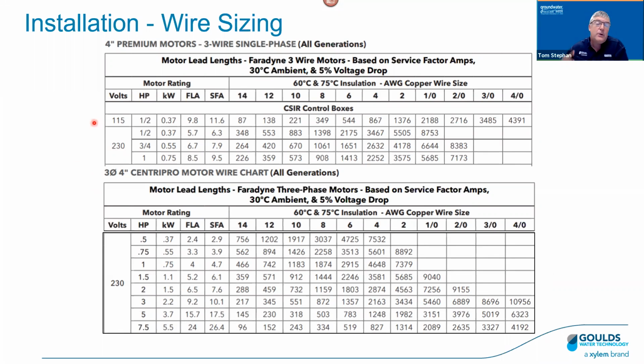So, one thing is we need to know the voltage, and we need to know the horsepower. If we have the model number, we have all that information. Manufacturers are all a little bit different, so it's a good idea to use the particular manufacturer's wire sizing charts, because the amperage does tend to vary a little bit. Once we know either the model number or, again, phase, voltage, and horsepower, then we can look at our charts. For example, in this case, a half 230, single phase 3-wire, this indicates that we can run 348 feet.